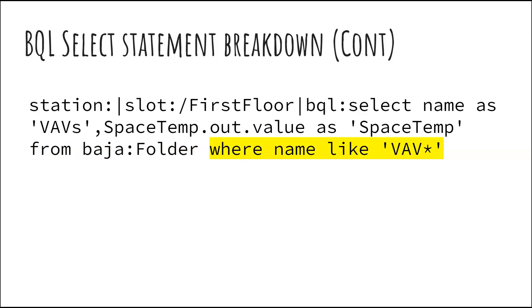The second half of our predicate is where we get far more specific with our filtering. Here we used 'where name like VAV*' — this removes any results that don't match the statement. We're looking for a folder whose name is like VAV and we added a wildcard to make sure we find them all. This section most commonly requires the most thought, but ultimately it's just a true-or-false statement that filters out results, which makes it simpler to figure out.